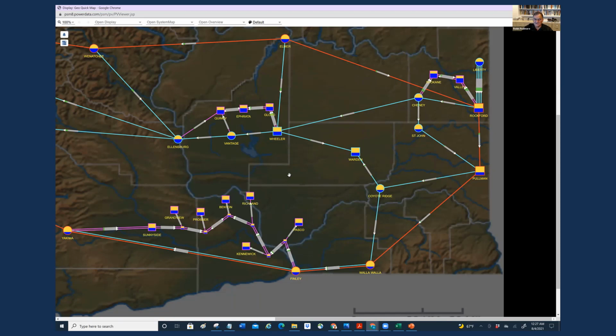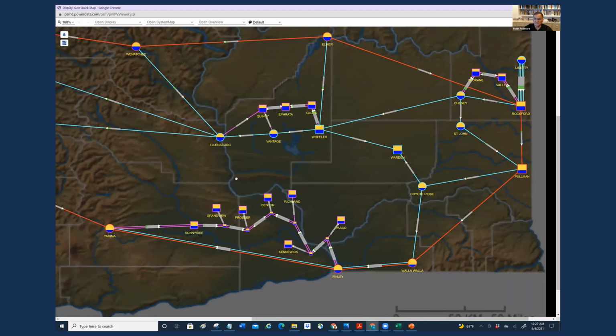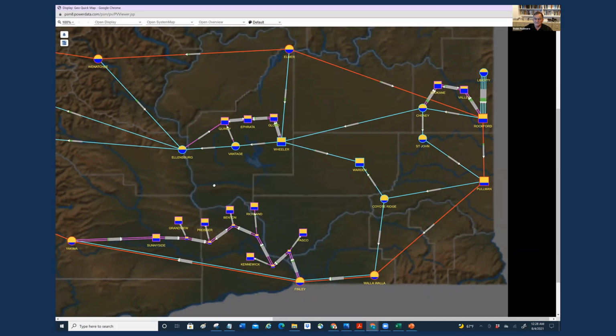The voltages are actually shown so that if it's nominal, we've got 50% orange, 50% yellow, 50% blue. When the voltage goes high, at 105, it goes all yellow. Goes low, it goes all blue. So it's analogous to someone in the water with a scuba mask. As they go up, they see more yellow. As they go down, they see more blue. So this gives a very nice graphical way of seeing the voltages in the system. Everything's within a nice 95 to 105% range right now.